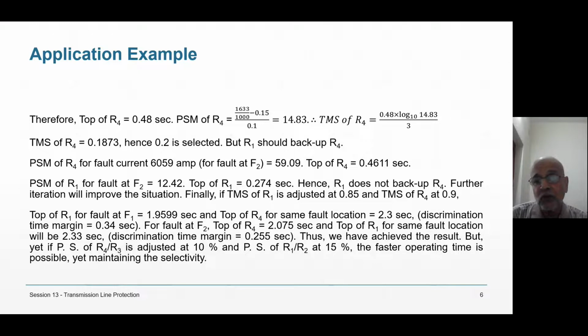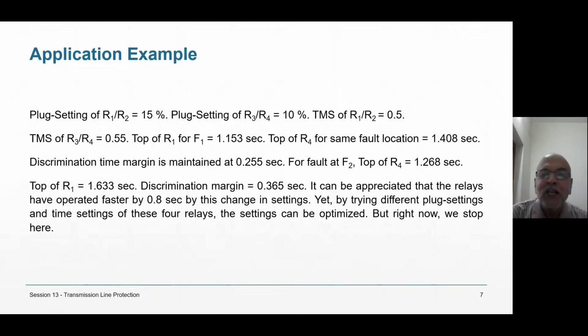But see, things are yet very complex. Had I taken PSM for R1, R2 at 15% and R3 and R4 at 10%, the discrimination margin would also have been maintained and the relays would have operated faster, by 0.8 seconds. In protection, if the relay operates faster, that is better. So in the second trial I changed the plug setting of R1, R2. I can yet go for a third iteration, a fourth iteration, and I may gain correct discrimination margin and yet the relays may operate faster.